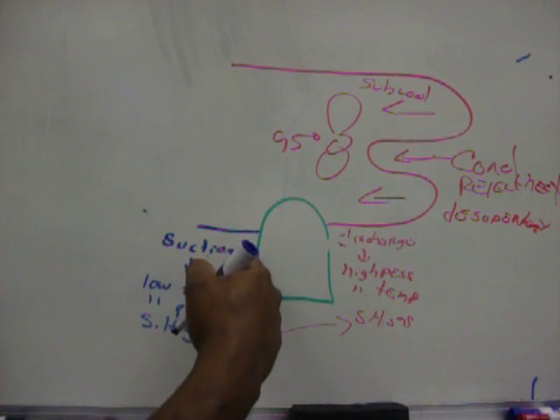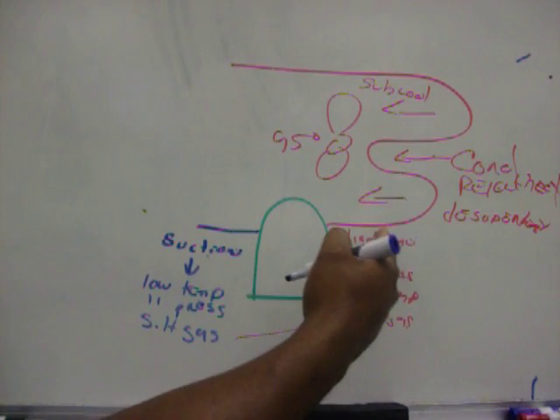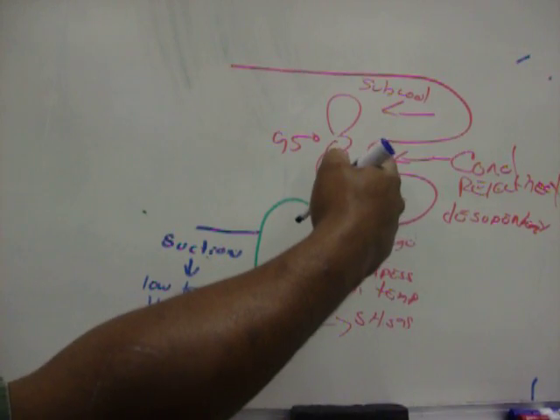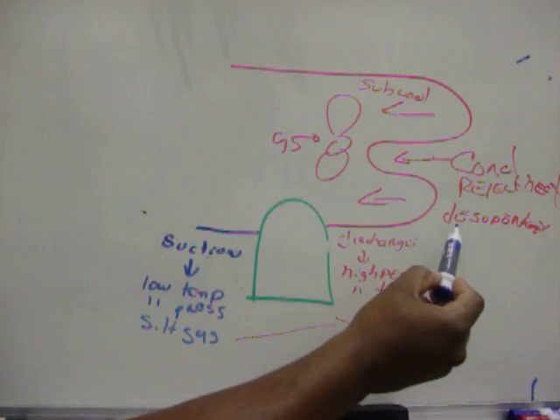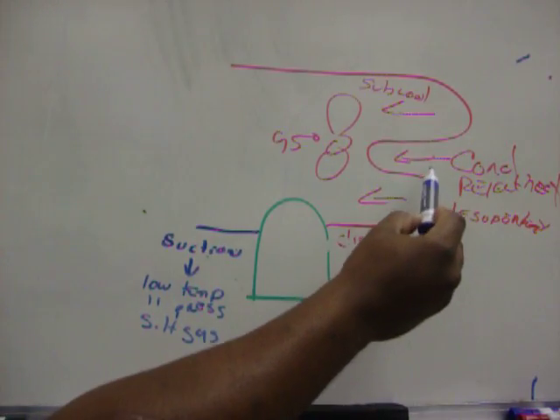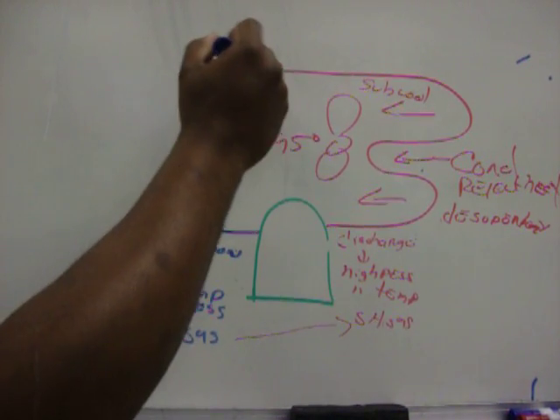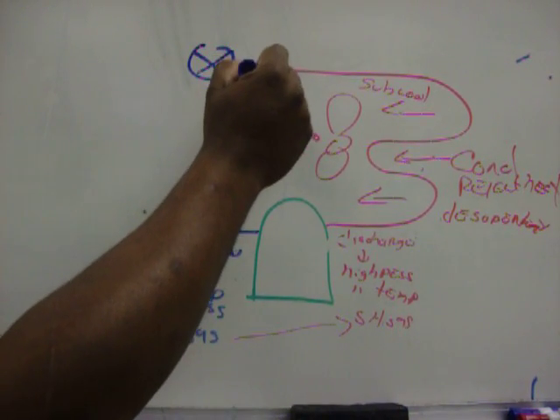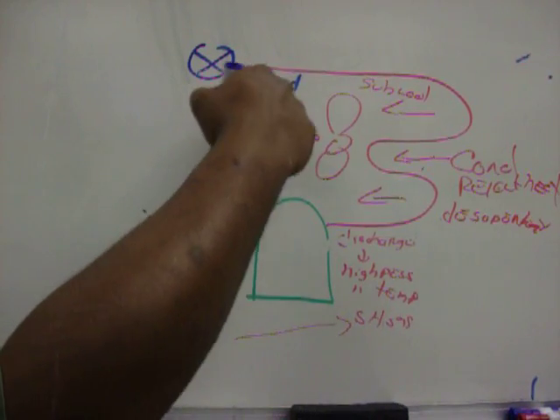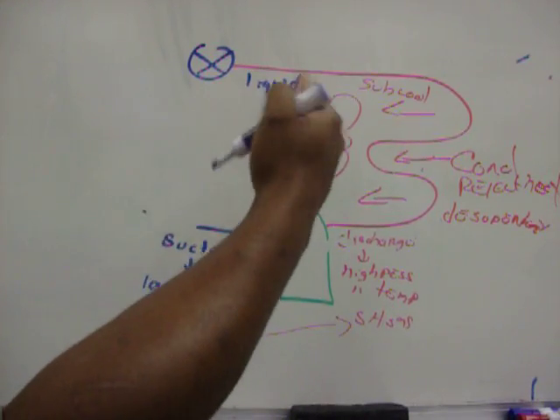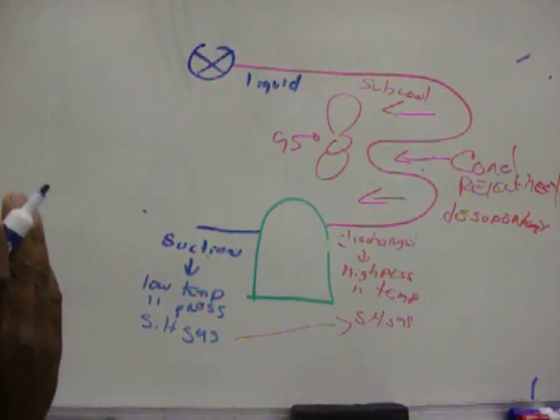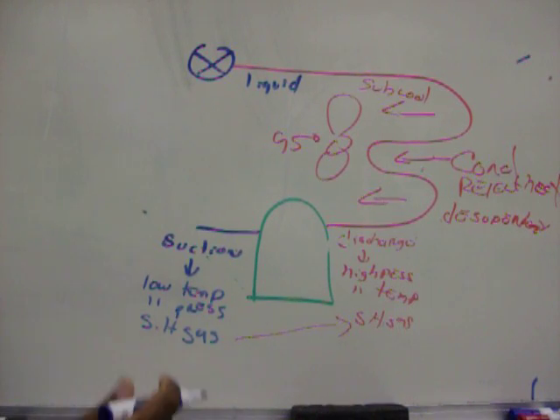So come in the compressor suction, compress it, go out discharge line. Discharge line to the condenser. Condenser goes in three phases: we de-superheat, we condense, and then we sub-cool. So now we're going to send 100% liquid. Now we're in the liquid line. State of refrigeration in the liquid line is a high-pressure, medium-temperature, sub-cooled liquid.